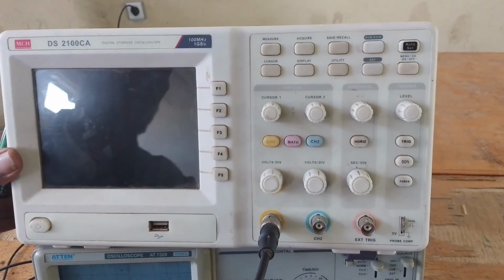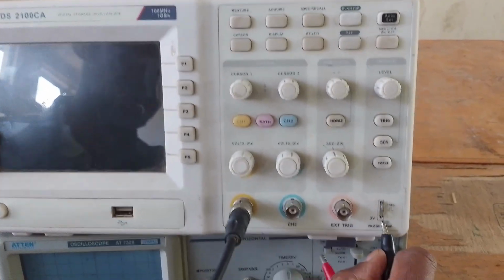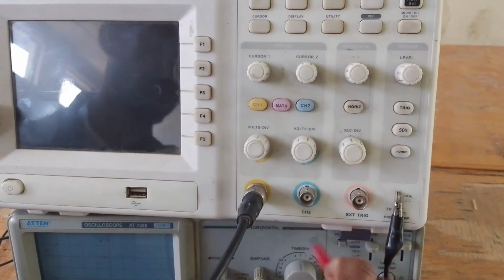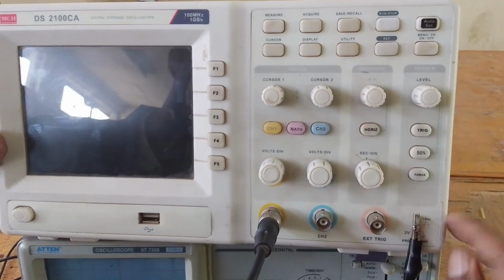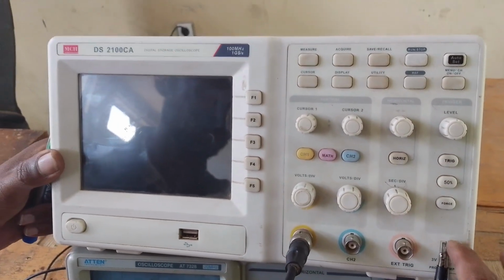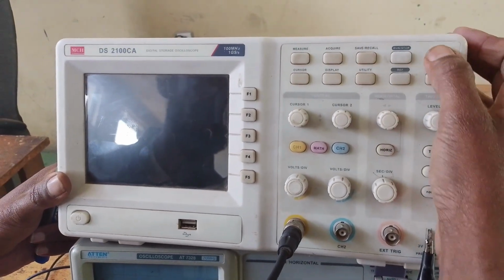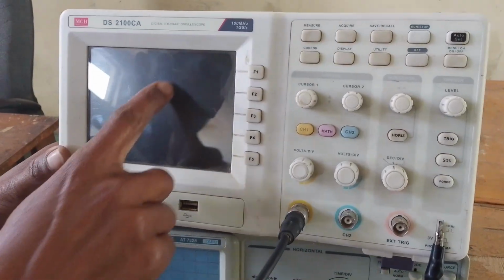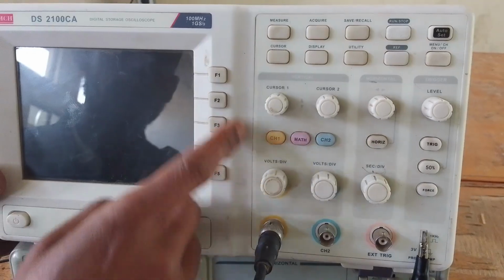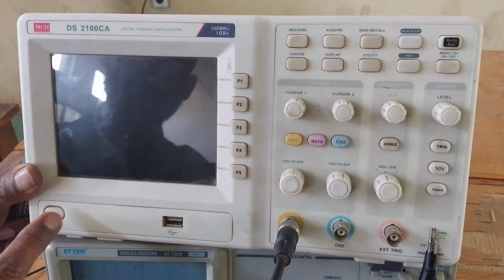The calibration method for digital is also the same as for analog. You can first give some ground for this one and check this one. Most of the time this reads a 1 kilohertz frequency, so our probe must be matched with these values. After that, you can adjust and see your output by using these additional components. So you will get that when powering this digital oscilloscope.